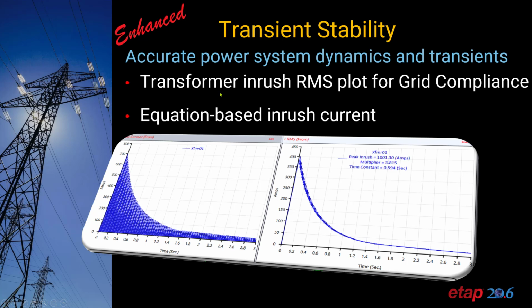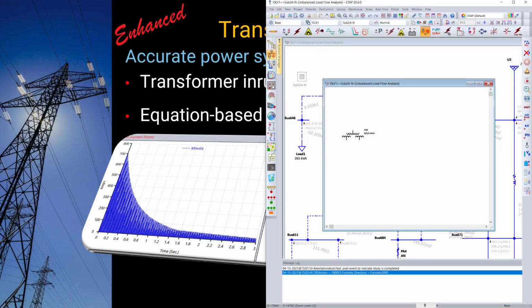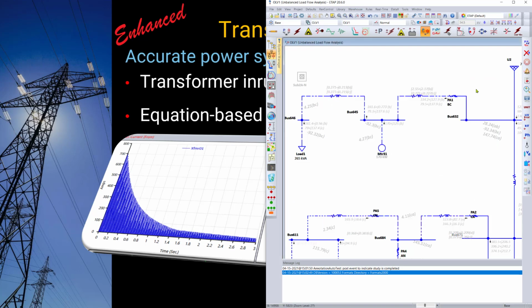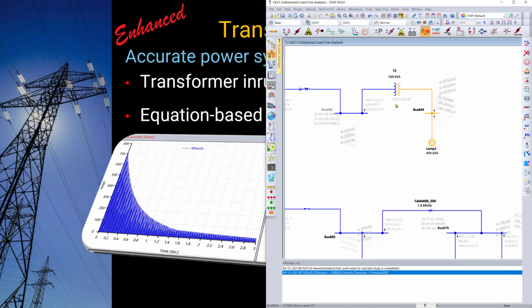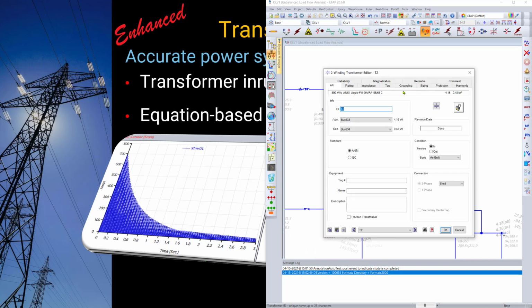Transient stability has been enhanced as well to include Inrush RMS plots that are meant for grid compliance. We saw these RMS plots when we looked at the plot views, where you can easily plot the instantaneous values as well as the Inrush peak. You can also see the Inrush value, the multiplier, and the time constant directly on the chart, allowing for deliverables to be more meaningful and more effective. The transformer editor within ETAP has also been modified so that you can essentially have an estimation of the Inrush curve directly in the program.